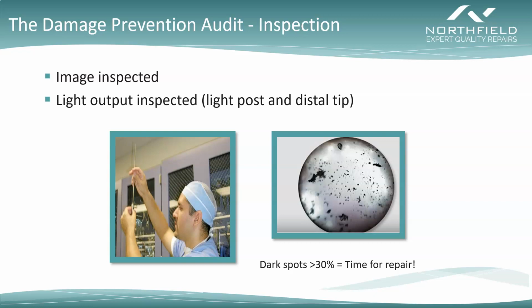It can be done every single time, very simply just by pointing the distal tip up towards a light. You can even use a small flashlight for this if you want. When you point the distal tip towards a light source, it's going to cause the light post to light up. And everywhere you see a dark spot, that is a broken fiber. Now, there are more fibers than what are needed in a scope, so you've got a little bit of margin for error. But typically our guidance is that if you've got dark spots in greater than 30% of the surface area, then that means that device needs to go out for repair.